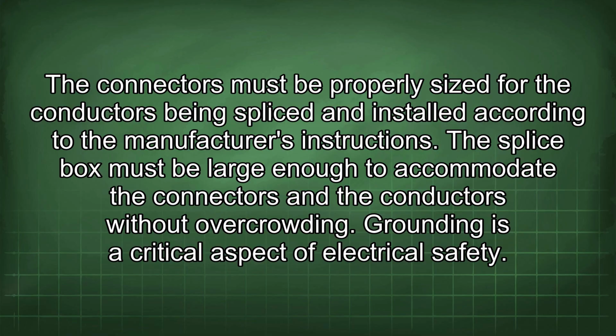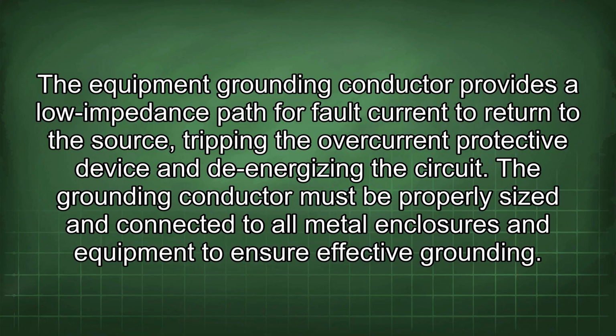Grounding is a critical aspect of electrical safety. The equipment grounding conductor provides a low impedance path for fault current to return to the source, tripping the overcurrent protective device and de-energizing the circuit. The grounding conductor must be properly sized and connected to all metal enclosures and equipment to ensure effective grounding.